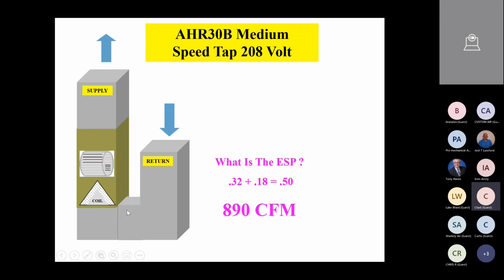I think the point of confusion is maybe it's not an open return. Maybe the return is boxed in, but the filter is at the air handler itself. Oh, okay. And that's where earlier I thought I heard you say at that point we're to penetrate the cabinet, but then that would be after the evaporator coil. Yeah, so let's say you actually have a filter in here. Come into the side of the cabinet and put a hole in, at the edge of the cabinet where it's convenient, and stick that pressure probe right underneath the coil, so you can read how much the fan is sucking against that filter, if at all possible. You understand what I'm saying? So let's say I had a filter right here. Let's say I had a box and I've got the filter.